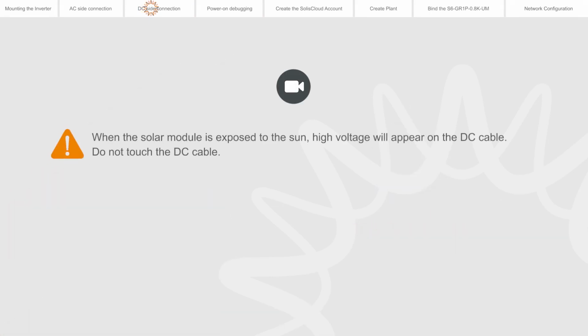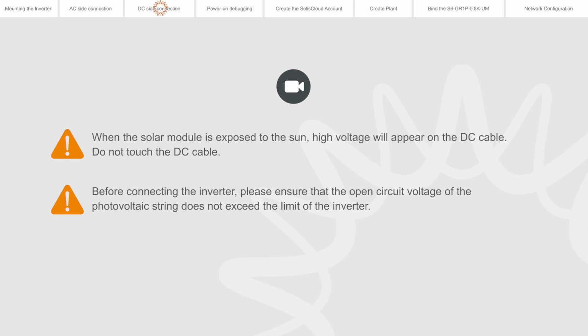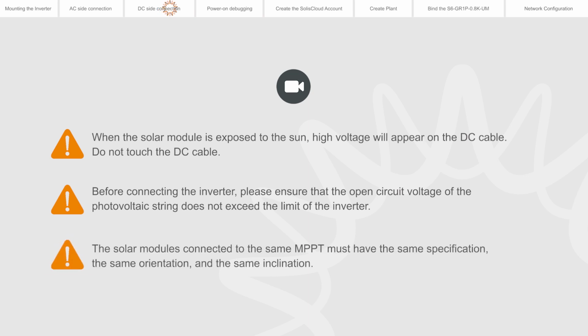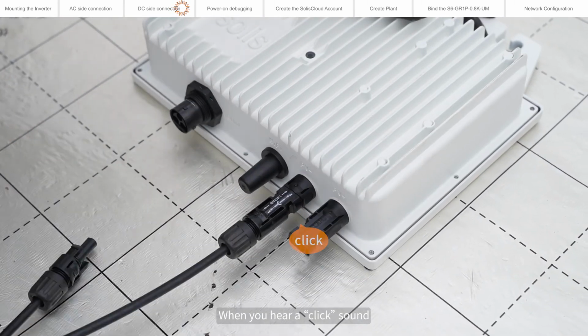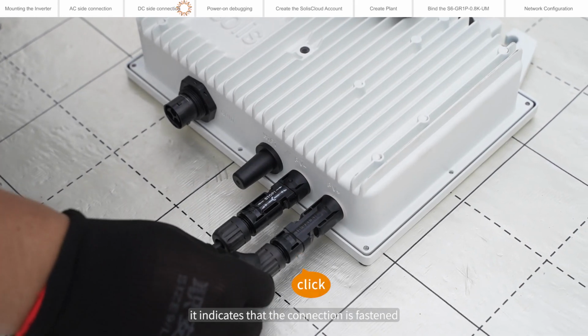When the solar module is exposed to the sun, high voltage will appear on the DC cable. Do not touch the DC cable. Before connecting the inverter, please ensure that the open circuit voltage of the photovoltaic string does not exceed the limit of the inverter. The solar modules connected to the same MPPT must have the same specification, the same orientation, and the same inclination. When you hear a click sound, it indicates that the connection is fastened.